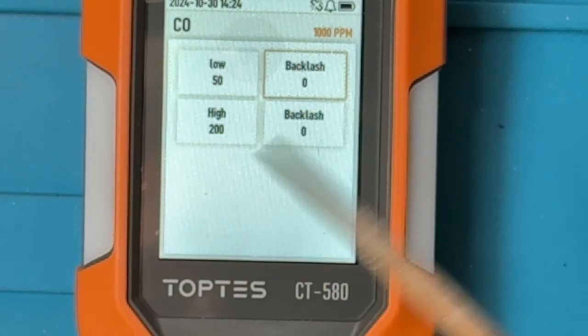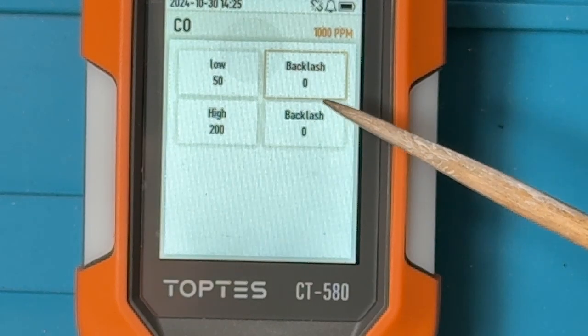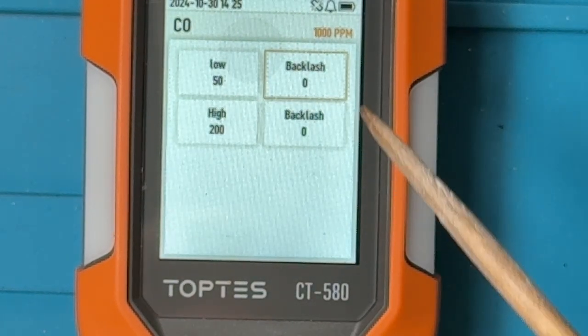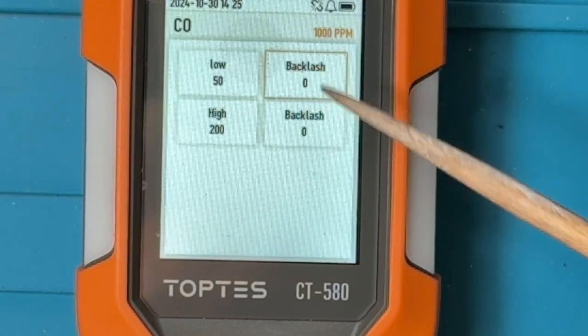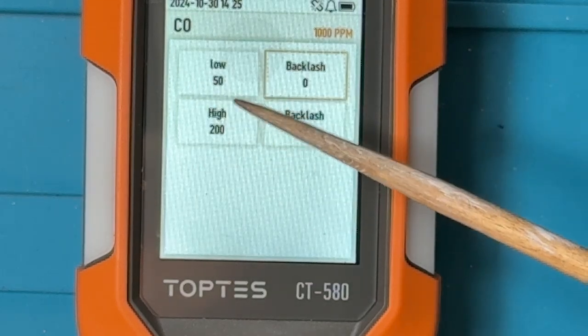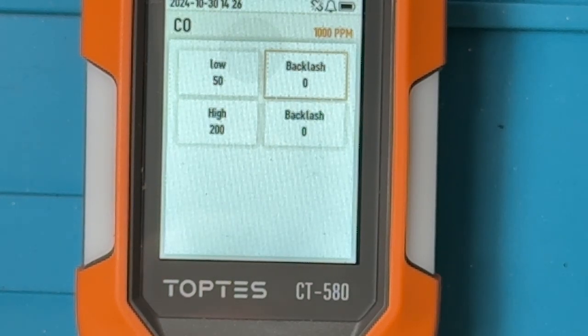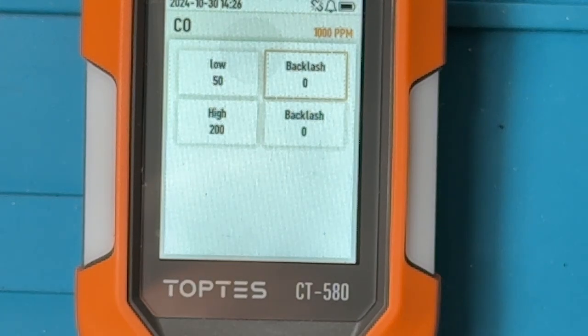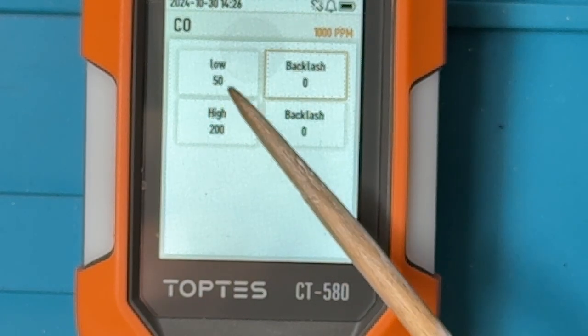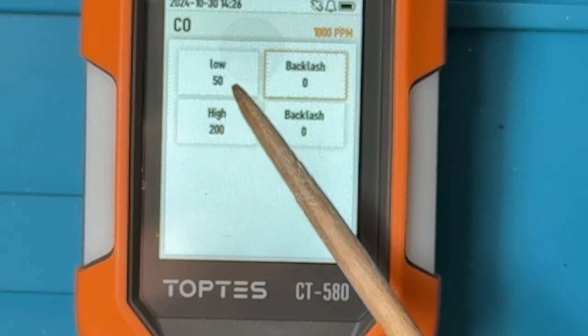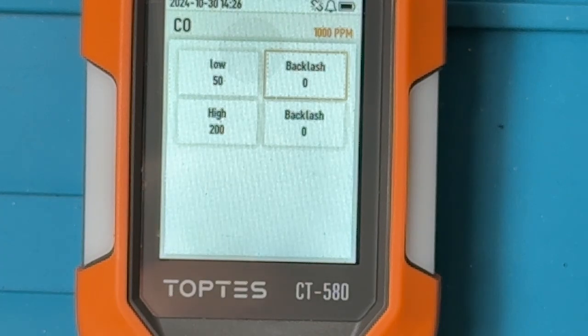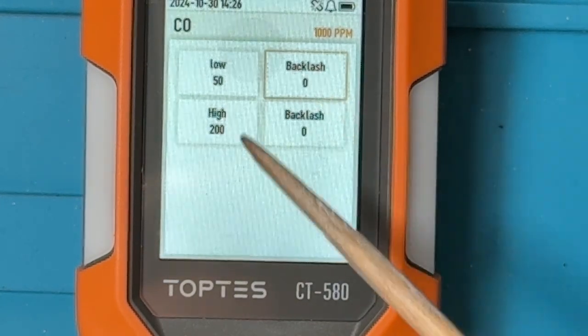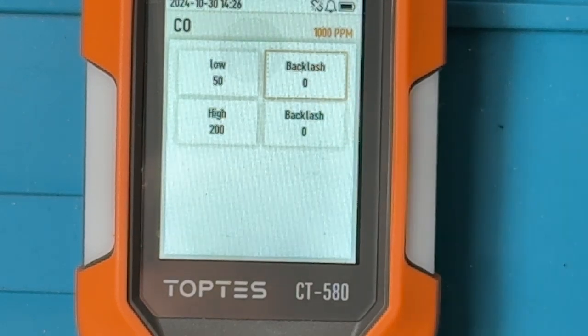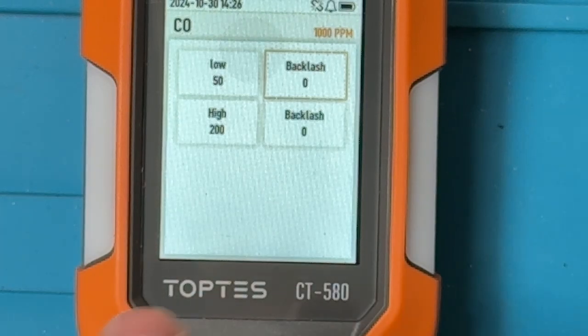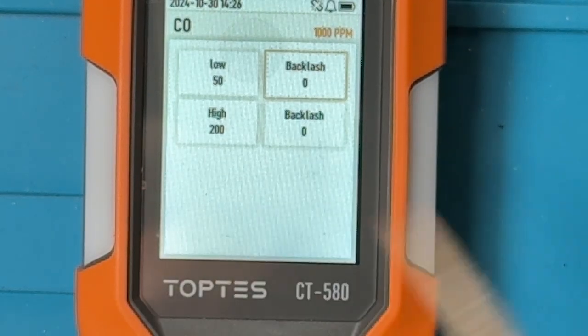In addition to that, we have these phrases where it says backlash. And this backlash is an interesting feature. The idea here is that when an alarm is triggered, we don't want to be in a situation where the alarm is going on and off and on and off, just because the concentration of carbon monoxide is going just above and below this threshold level. So for example, the alarm will go off when it goes above 50, and when it goes below 50, the alarm stops sounding. The idea of the backlash, both for low and for high, is we can set a value which says that the alarm will keep operating until the carbon monoxide concentration drops some number of units below that threshold.